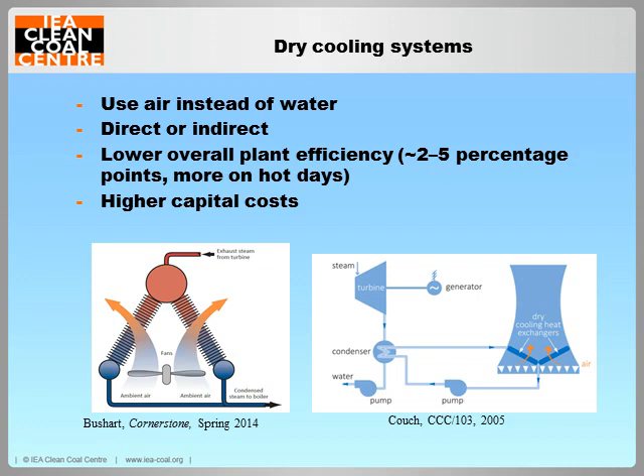The main disadvantages of dry cooling are higher capital costs, a lower power efficiency and a larger footprint than a closed-loop wet cooling system of comparable capacity. Overall, plant efficiency is lowered by about 2 to 5 percentage points, and this can be even higher on hot days, though it does depend on the type of plant. This is because air is a less efficient cooling medium than water. Unfortunately, lower efficiency means more coal is needed per unit of electricity, which in turn can lead to higher CO2 emissions.